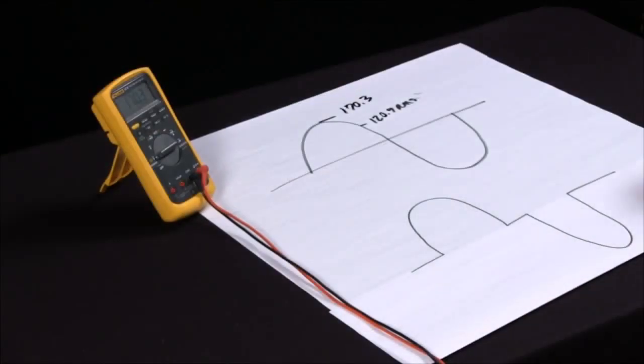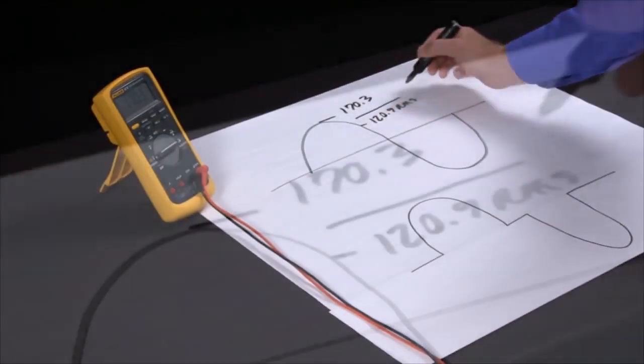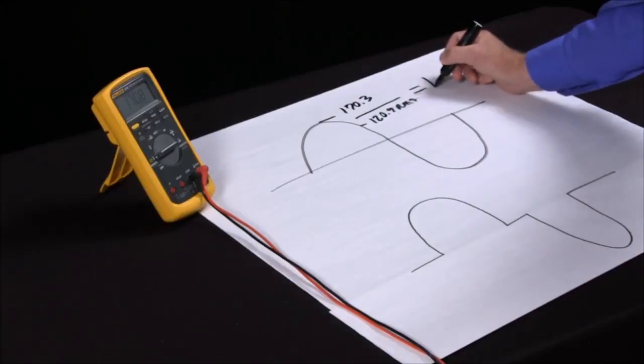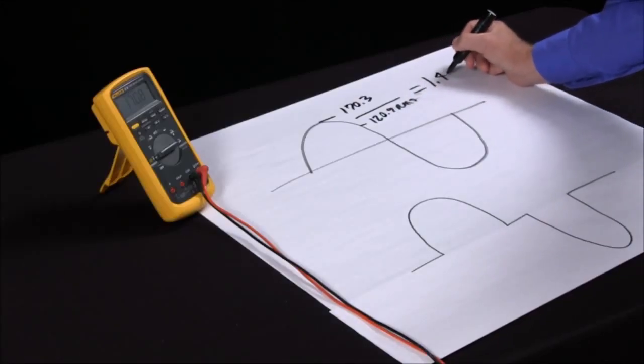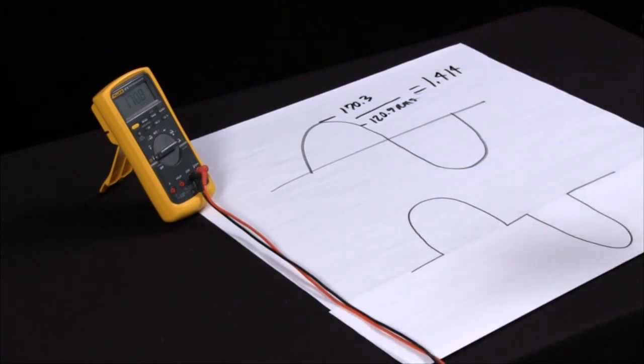Now there's something called the Crest factor, which if I divide the RMS into the peak on a nice clean sine wave, this should come to 1.414. Now we can all divide 120.9 into 170.3 and come up with 1.414. Yeah, maybe if we're Rain Man.